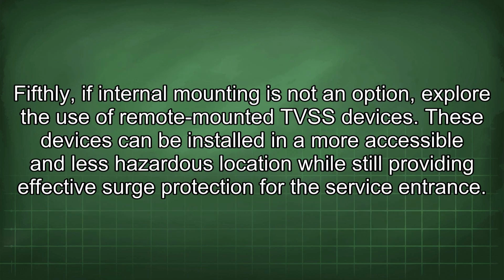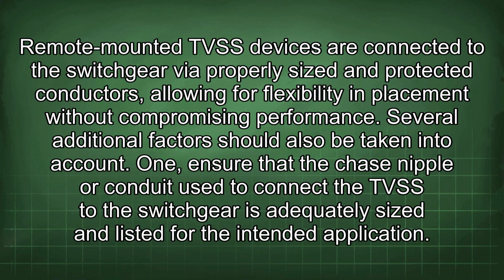Fifthly, if internal mounting is not an option, explore the use of remote-mounted TVSS devices. These devices can be installed in a more accessible and less hazardous location while still providing effective surge protection for the service entrance. Remote-mounted TVSS devices are connected to the switchgear via properly sized and protected conductors, allowing for flexibility in placement without compromising performance. Several additional factors should also be taken into account.